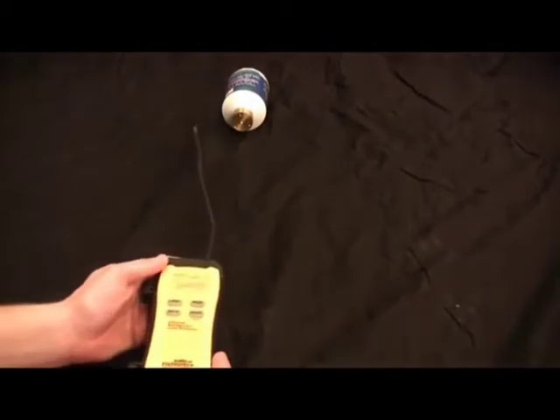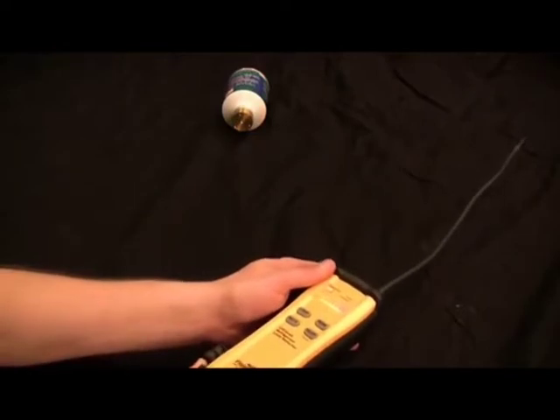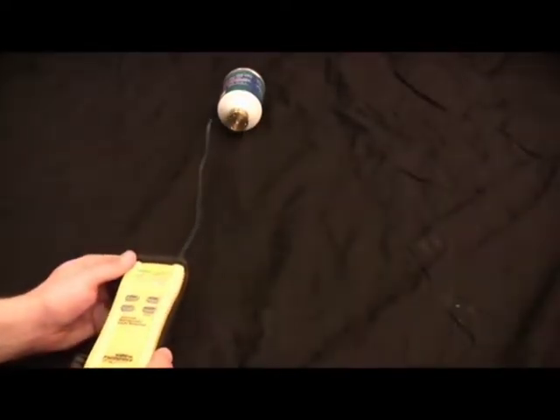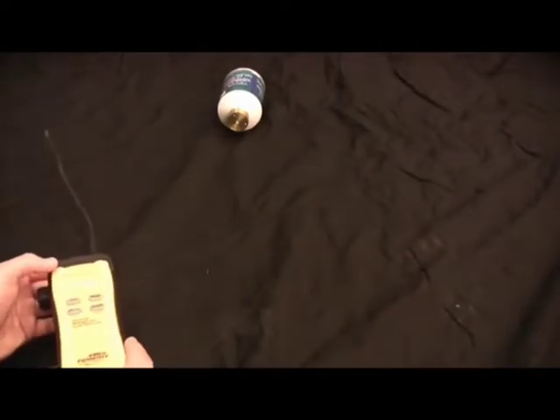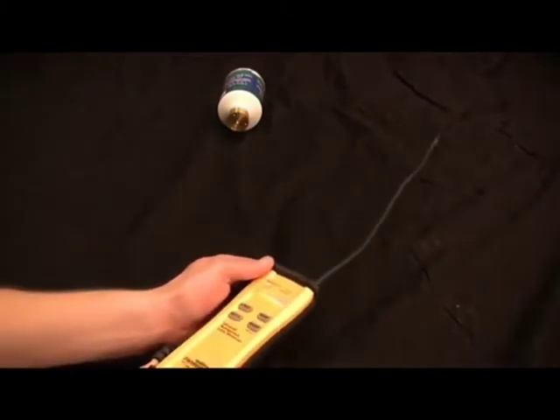And so this is what we call the sweeping method. And you just want to dial it in until that buzzer stops going off. Now this is a pretty big leak for high sensitivity. However, if I hover over it, this is a common mistake that people use with infrared leak detectors. If I hover over it, it will stabilize to that level.